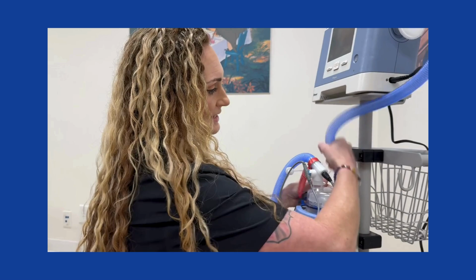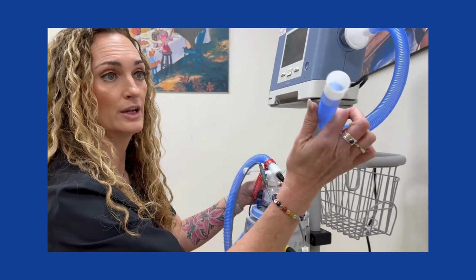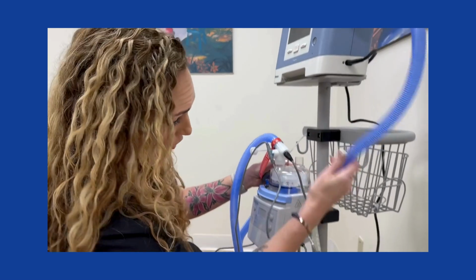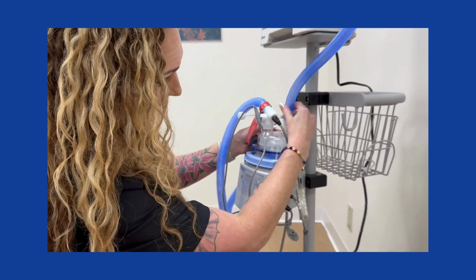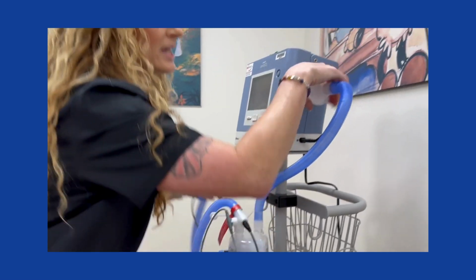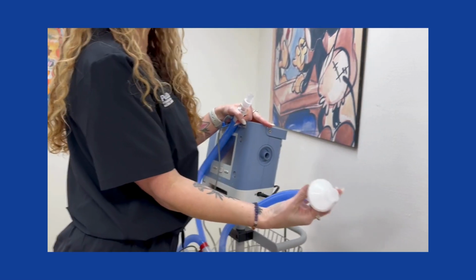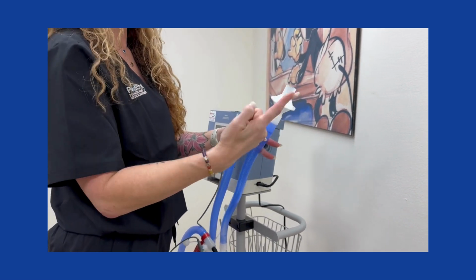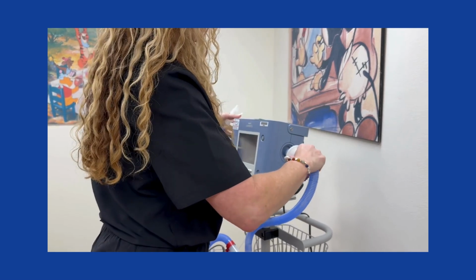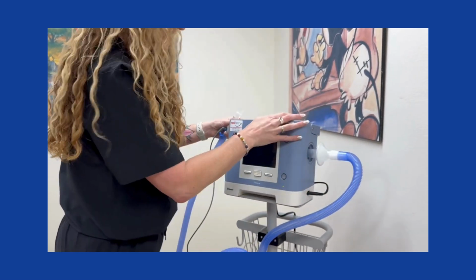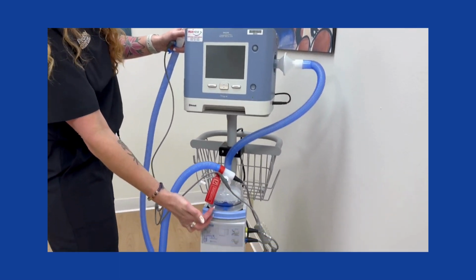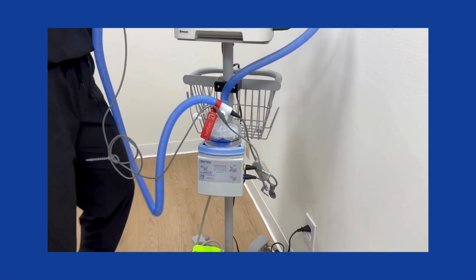Your short piece that also comes in the circuit, all right, one end, it doesn't matter which end, will go on the other opening of the water chamber, and then the other end will go here. And again, this is your filter, it just pulls off. So you're going to change the filter and the circuit. And then you're going to slide it right back on. Make sure you have water in your chamber, never fill it past the line, and then you are good to go.